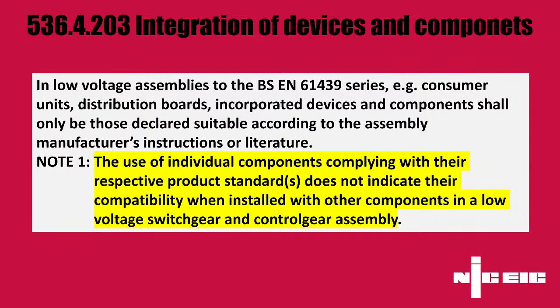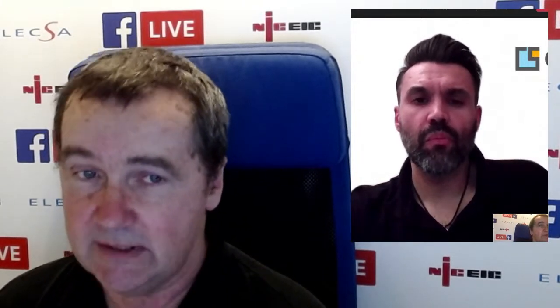But no, very, very interesting question, because it's made clear in that set of regulations that the use of individual components that comply with their respective product standard doesn't indicate that their compatibility when installed with other components will mean that the low voltage switchgear or control gear assembly is compliant. So really an interesting point, and that's the reason why we get concerned about mixed manufacturers equipment within the same assembly.